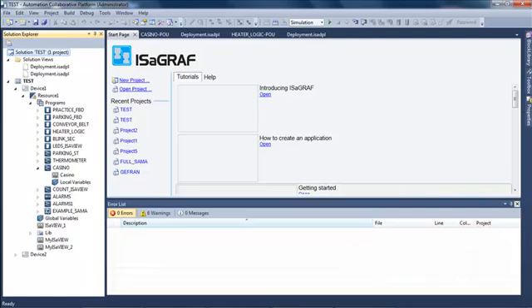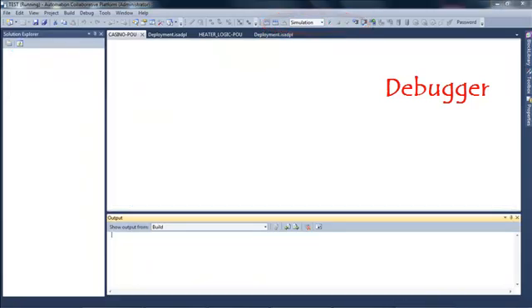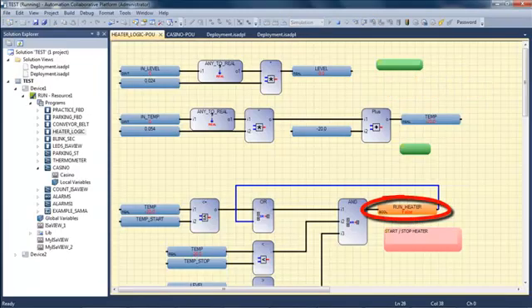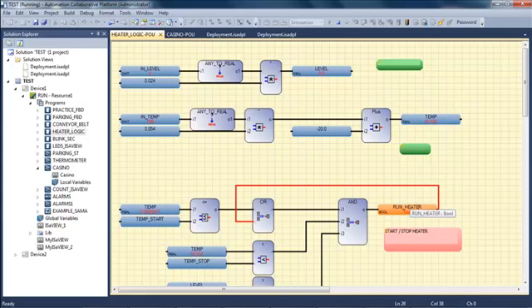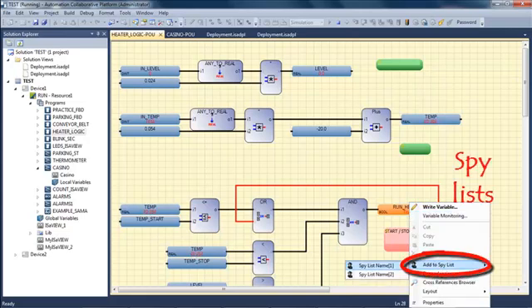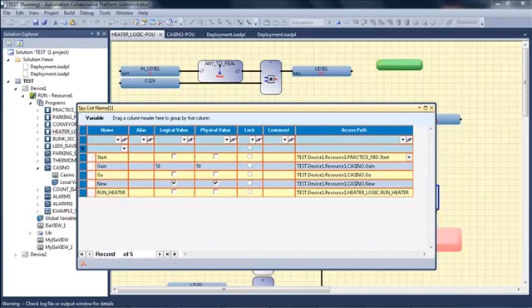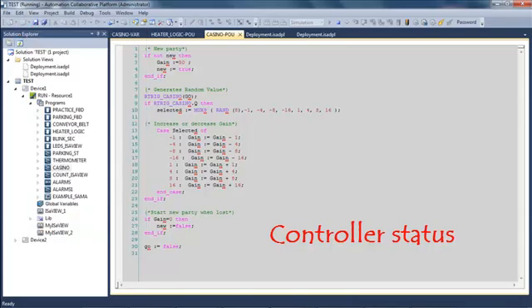When compilation is done, I can debug or simulate my project. I will start the simulation. In an FBD program, for example, I can double-click on a variable to change its value or lock/unlock it. I can also display a variable in a SPYLIST, which is a list of selected variables I want to monitor. Another plugin is the locked variable viewer, which shows all currently locked variables. There is also the controller status plugin, showing the cycle time, the number of locked variables, and so on.